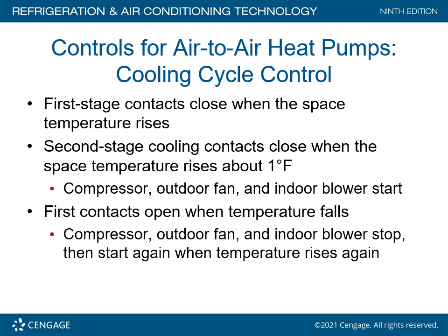Controls for the air-to-air heat pumps, cooling cycle control. First stage contacts close when the space temperature rises. Second stage cooling contacts close when the temperature rises about 1 degree Fahrenheit. Compressor, outdoor fan, and indoor blower will start. The first contacts open when the temperature falls, and the compressor, outdoor fan, and indoor blower stop, and then start again when the temperature rises. So it just operates as a standard thermostat, nothing magical about it. Remember, the thermostats that you're going to utilize in this heat pump installation today will all be digital.